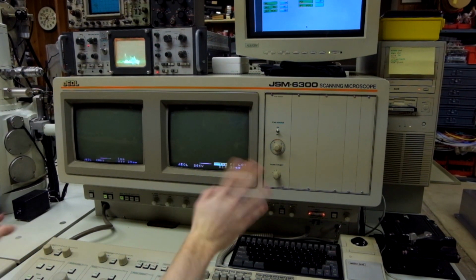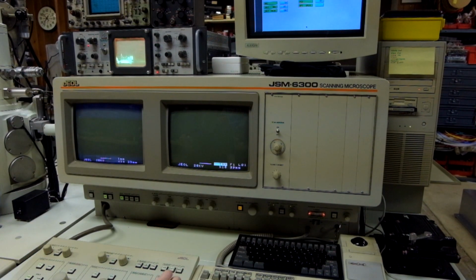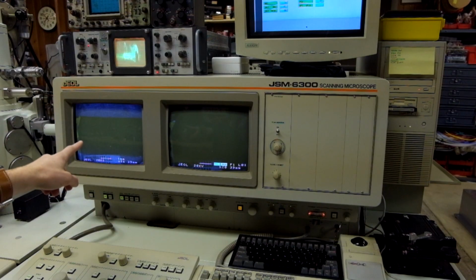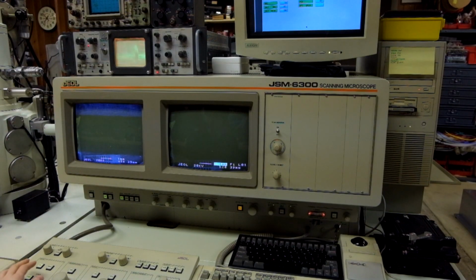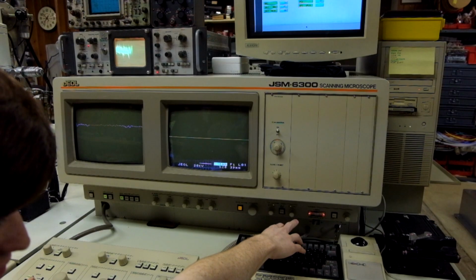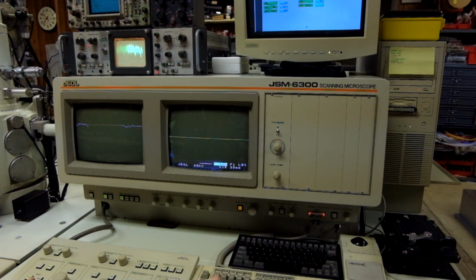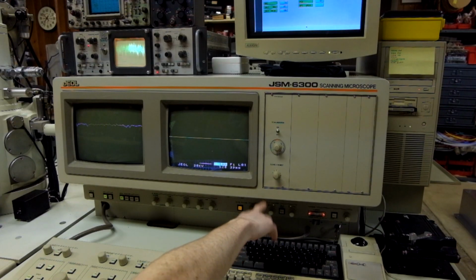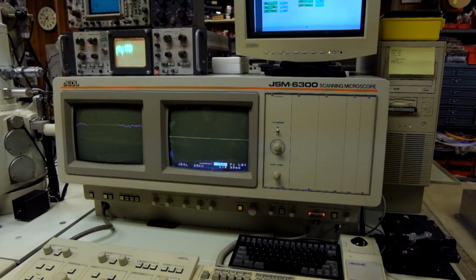So without even touching anything else right now, I can adjust that in brightness and contrast, and we can see an actual image of what's going on in the chamber. So I'm not going to touch that right now. I'm going to quickly make sure that the filament is saturated, and right now we're putting around about 70 microamps out, and I'm going to make sure that's saturated, and I'm going to align the gun for tilt and shift and a couple of other things, and then we'll be ready to go.